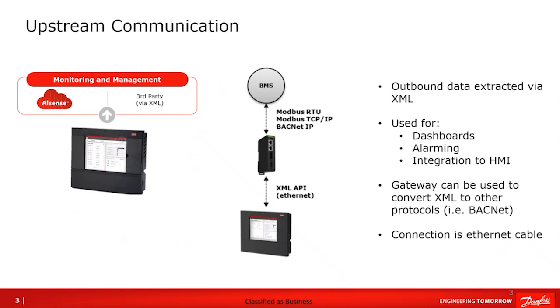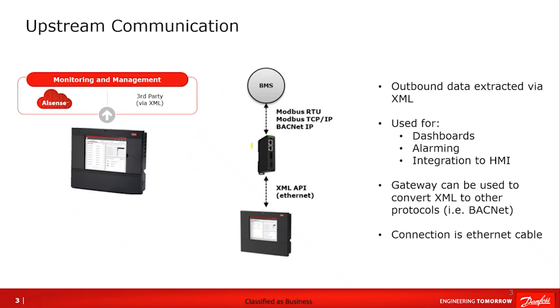If the formatting of the data needs to be in a different format, something like Modbus or BACnet, that can be accomplished. It would just require a gateway — like we have pictured in the middle here — so that gateway would take that XML data out of the System Manager and convert it into the other format needed to allow for that HMI or secondary interface to properly display the data.